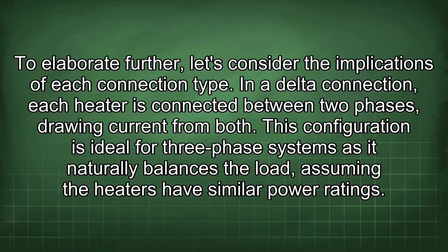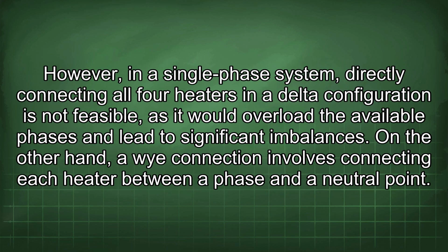To elaborate further, let's consider the implications of each connection type. In a Delta connection, each heater is connected between 2 phases, drawing current from both. This configuration is ideal for 3-phase systems as it naturally balances the load, assuming the heaters have similar power ratings. However, in a single-phase system, directly connecting all 4 heaters in a Delta configuration is not feasible, as it would overload the available phases and lead to significant imbalances.